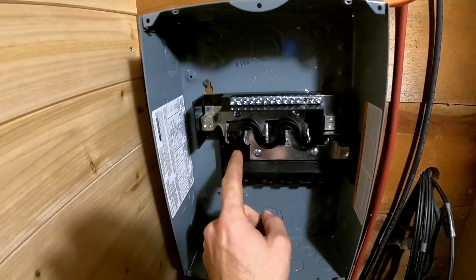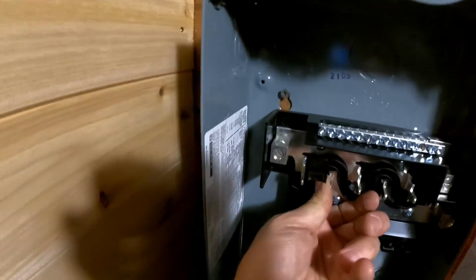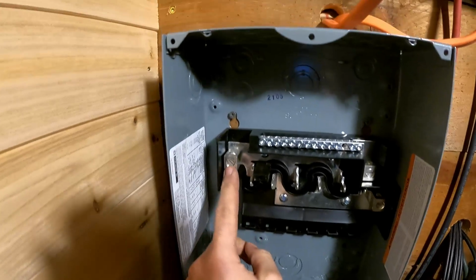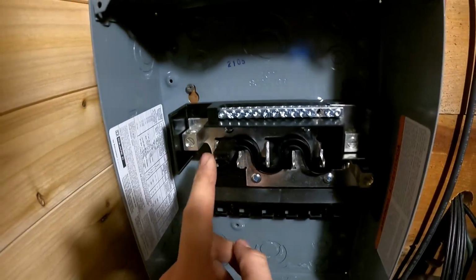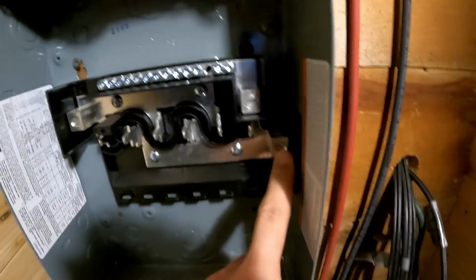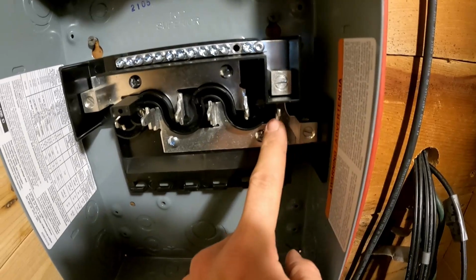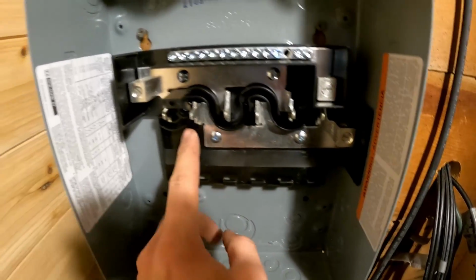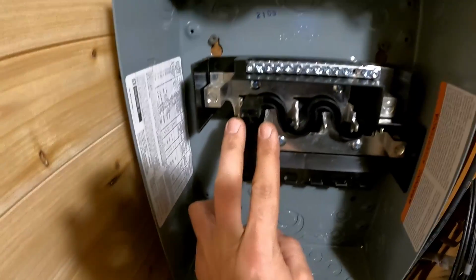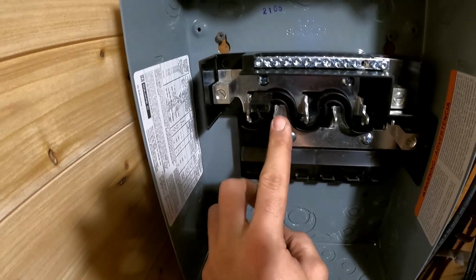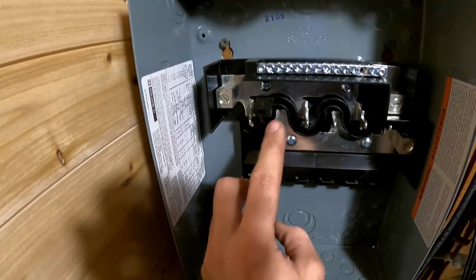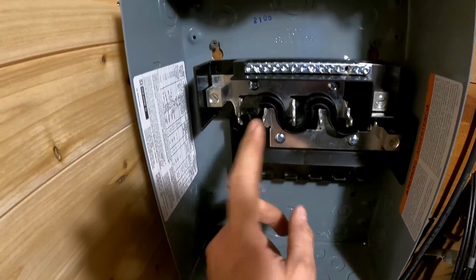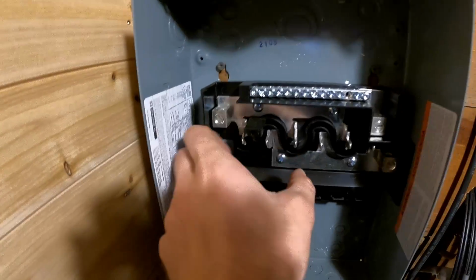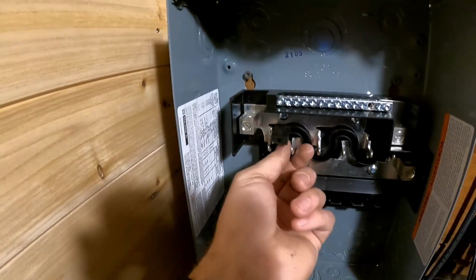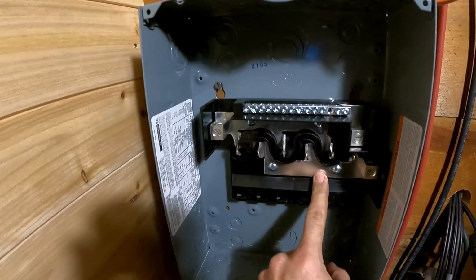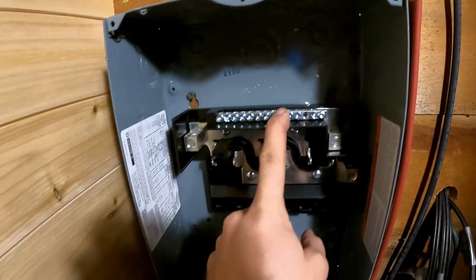This panel can do two phase. So here's one phase, and it goes to all the top breakers. Here's the second phase lug, and it goes to all of the bottom breakers. If you installed any two breakers side by side, one phase would be on one, the other phase on the other, since they alternate. So if you have a two gang breaker, it'll always be two phase because they alternate. And this here is neutral.